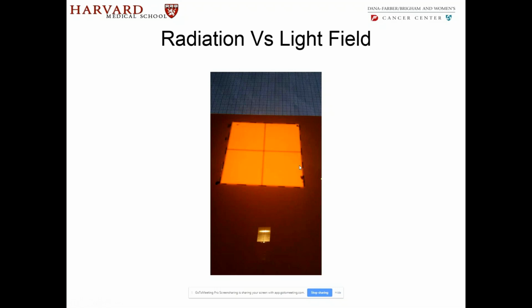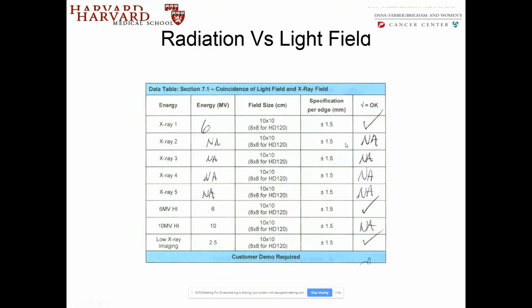If the film irradiation matches this to within plus or minus 1.5 millimeters, there are specifications for different field sizes for a given energy. So this is a 10 by 10 field size for 6 MV energy in this case. If it does match to within that, I accept it. If it does not, then it has to go through the process of the Varian engineers, who will adjust it and take a look at it and make sure.